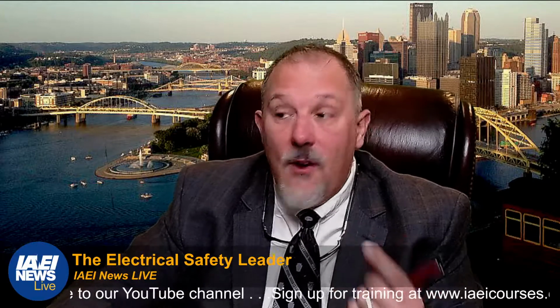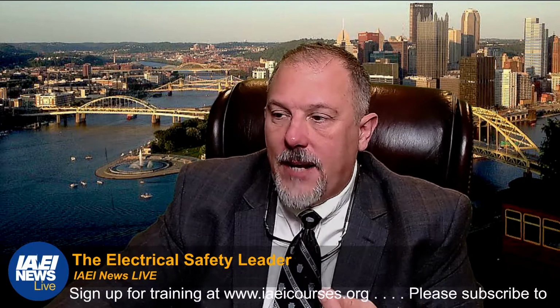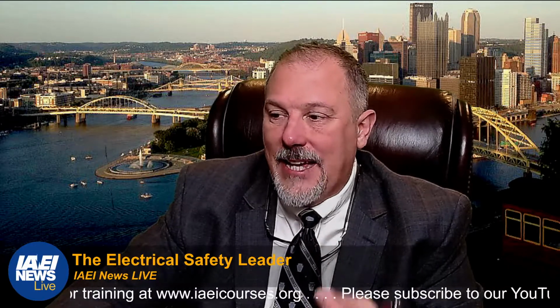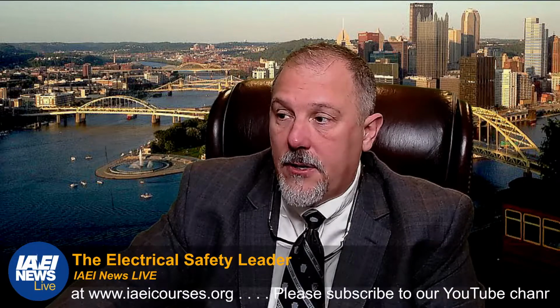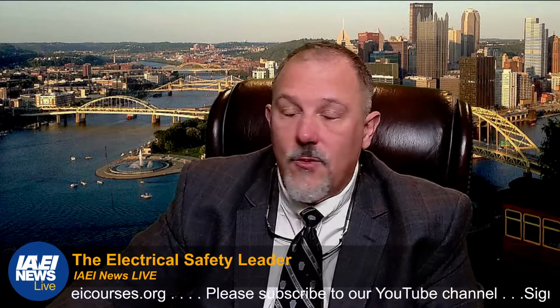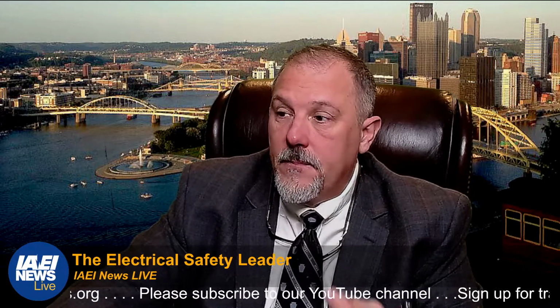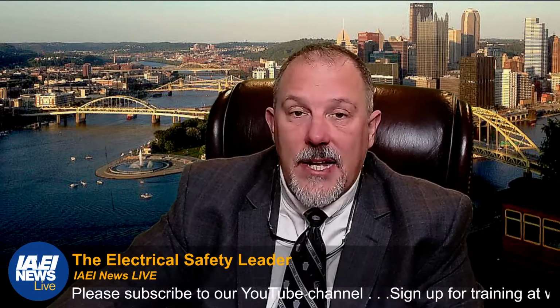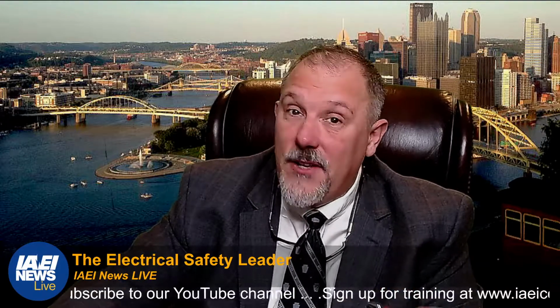So you say, well how often, Tom, do I have to do that? You've got to go to Chapter 10. Chapter 10 talks about test frequency for a molded case circuit breaker. Equipment condition, we're going to say it's in good condition. Mechanical operation and cycling, which we were just talking about, every 5 years.